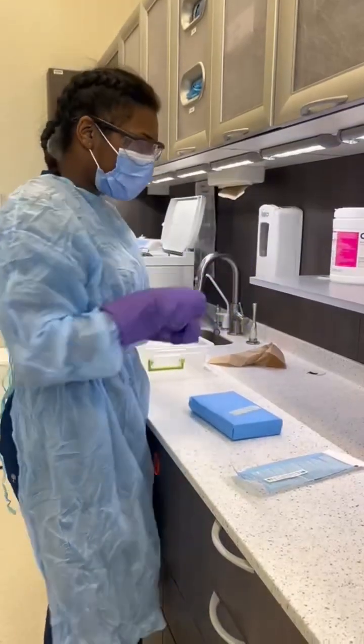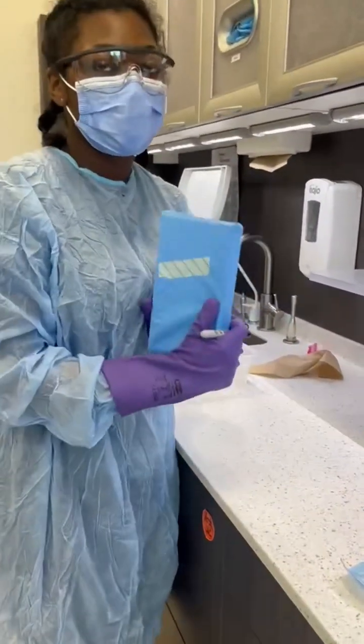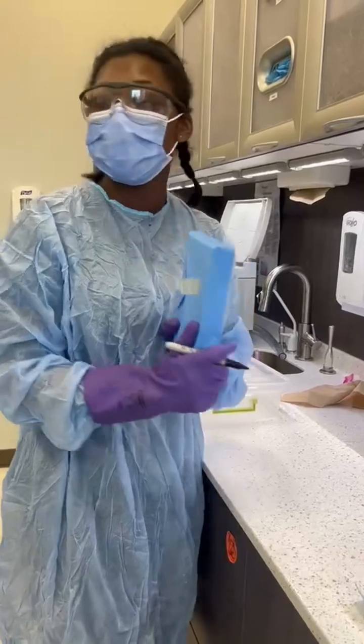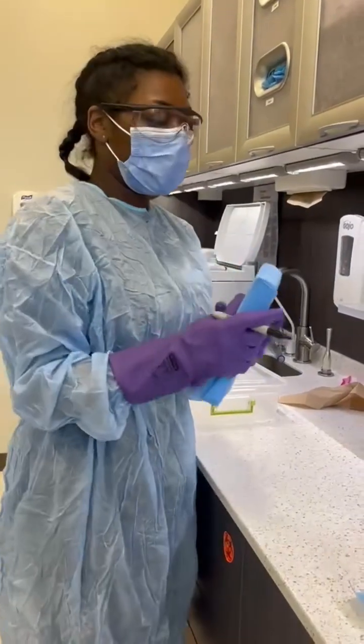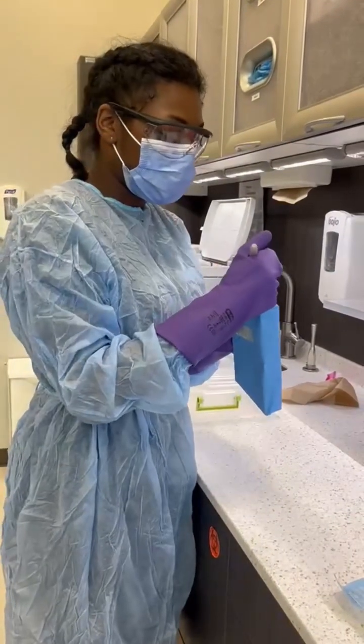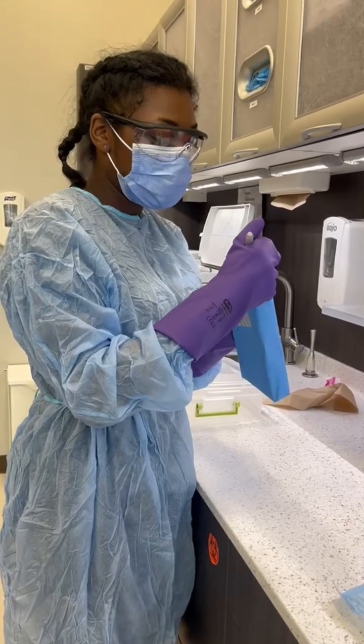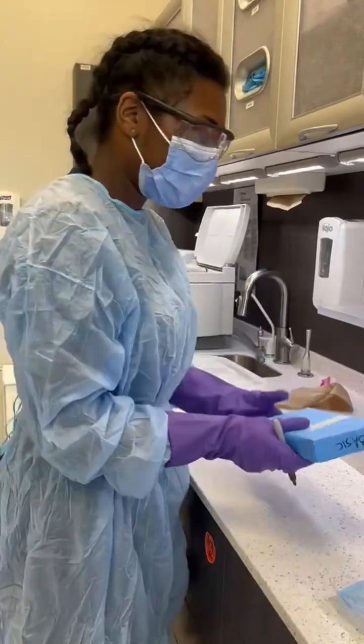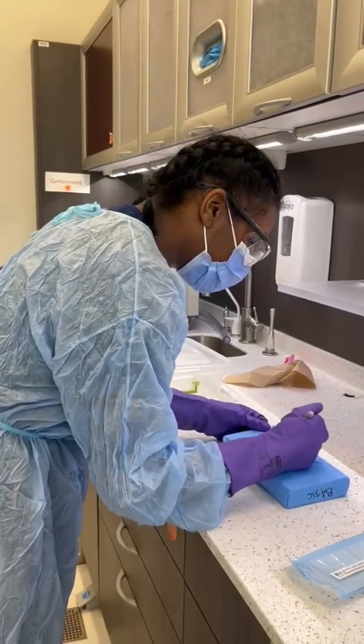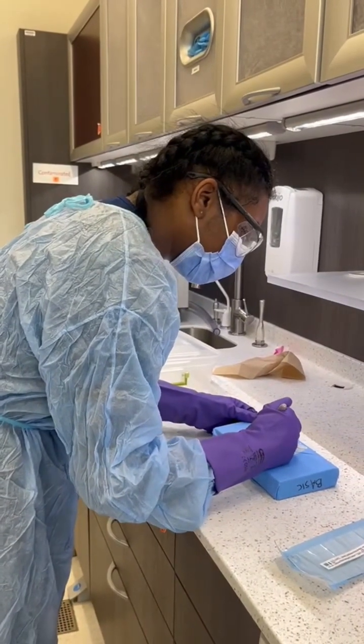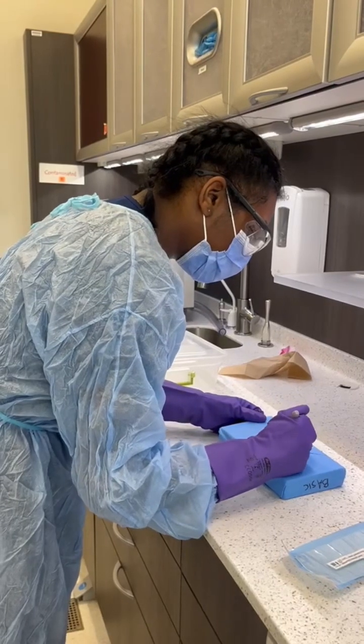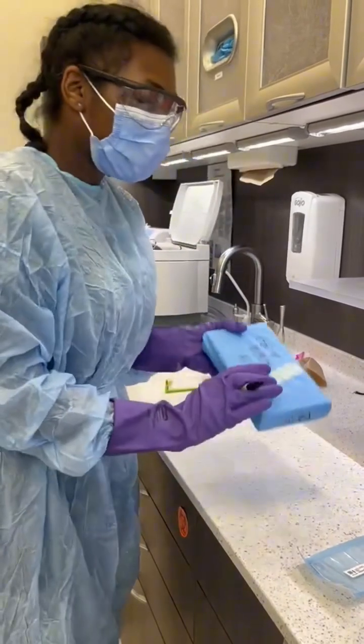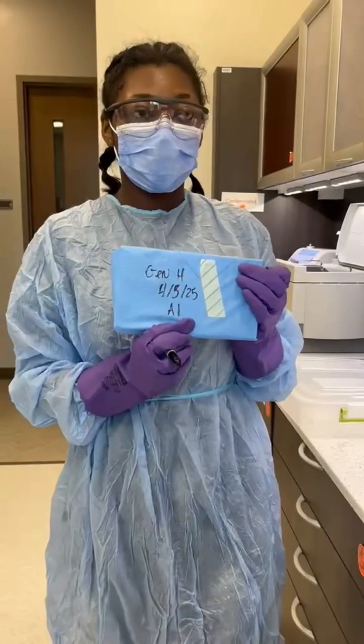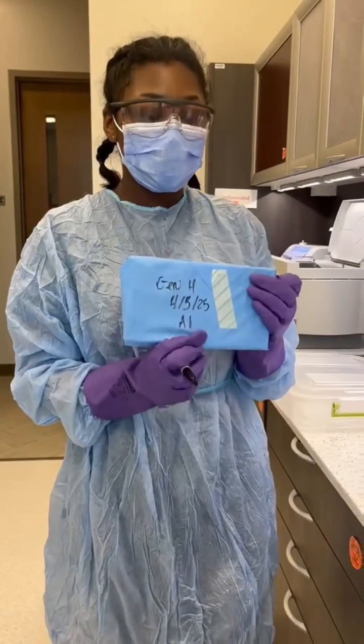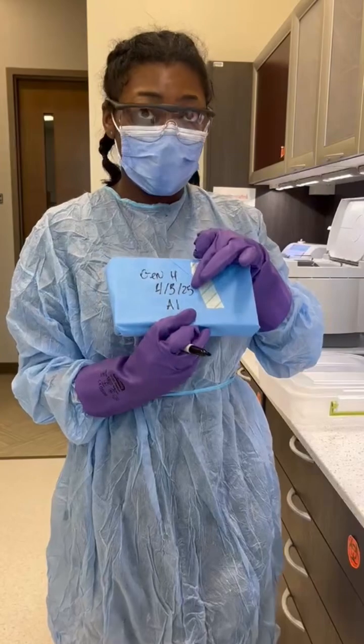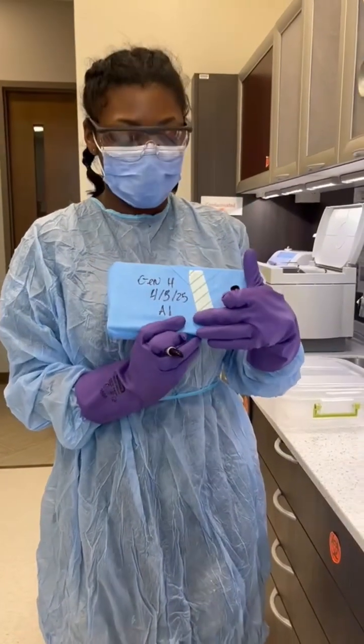You want to write on the side what type of cassette this is so that it doesn't have to be opened and risk contamination when putting it away, so that the next person that uses these instruments knows what instrument set this is. And this is a basic set, so you just write basic on it, as well as your name, the date, and once again, which sterilizer. You always put the sterilizer that it is going into so that we know if the sterilizer malfunctions, and if it doesn't get clean, we know what day it was and which sterilizer stopped working.